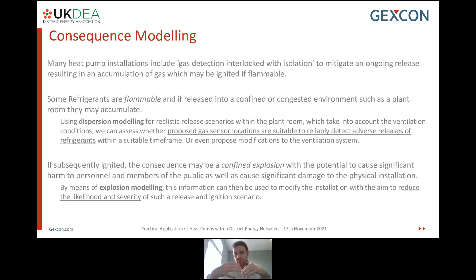So the idea with conducting dispersion modeling in this particular case would be to assess different types of releases and test the proposed gas detector system to reliably detect adverse releases of refrigerants into an enclosed environment. And if it's a flammable gas, we could also conduct explosion simulations to assess the impact of overpressures in the building and potential damage it could incur to the installation. So the idea with the explosion model would be to reduce the likelihood and severity of such release and ignition scenarios.